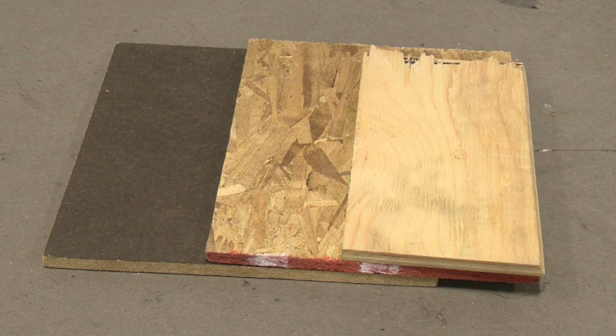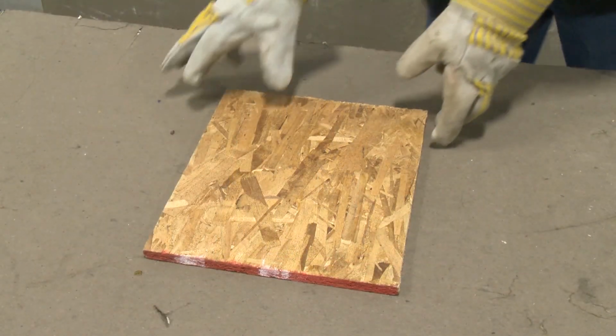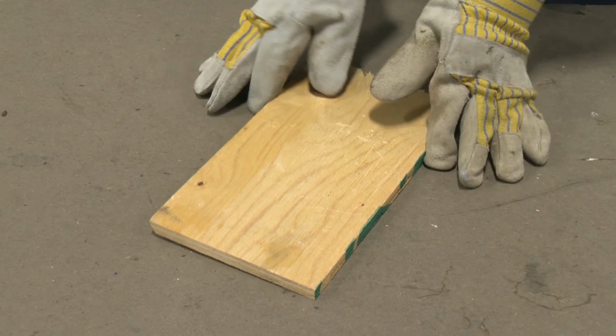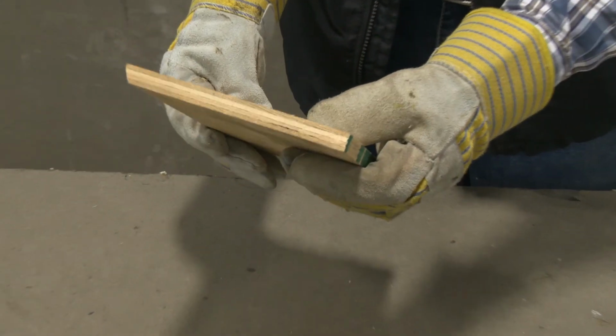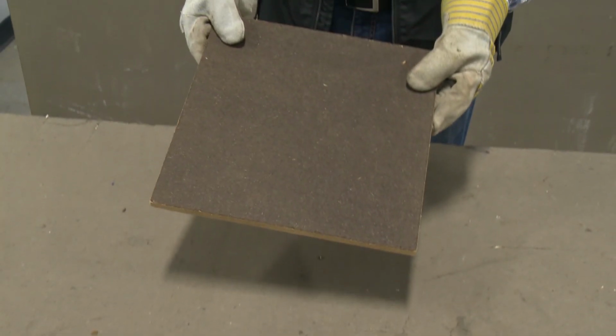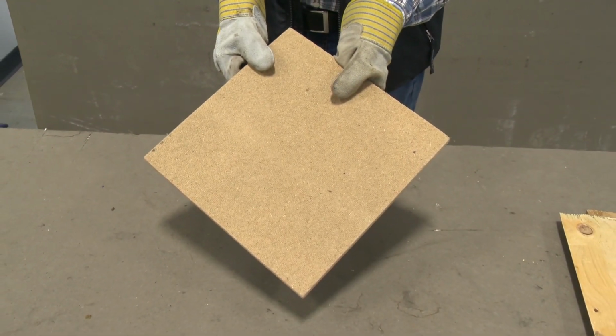Some substrates are more susceptible to ignition and burning during open flame applications. Oriented strand board, or OSB, plywood, and dimensional wood must be prepared, treated, and covered to reduce the risk of fire. Wood fiber insulation may smolder for hours with minimal exposure to the torch flame and must be protected in all instances.